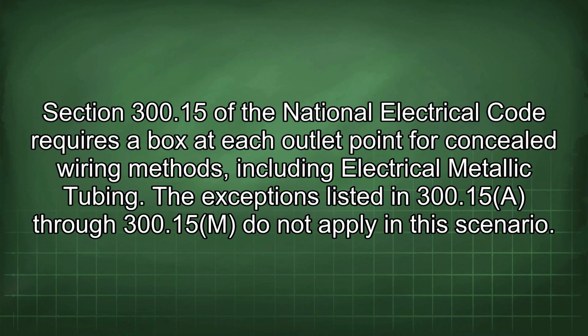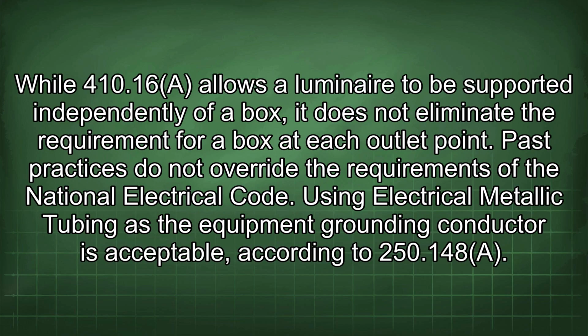Section 300.15 of the National Electrical Code requires a box at each outlet point for concealed wiring methods, including electrical metallic tubing. The exceptions listed in 300.15 through 300.15m do not apply in this scenario. While 410.16 allows a luminaire to be supported independently of a box, it does not eliminate the requirement for a box at each outlet point. Past practices do not override the requirements of the National Electrical Code.